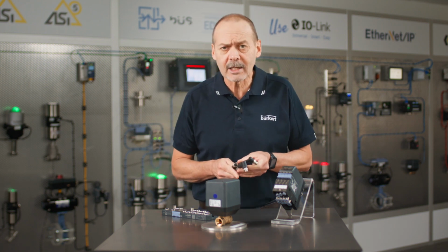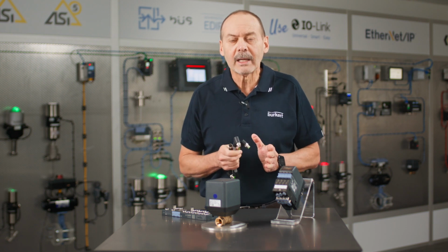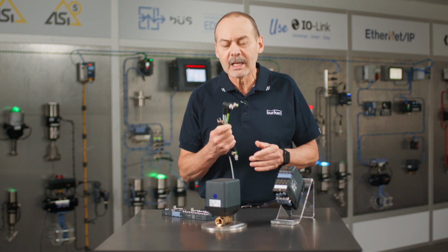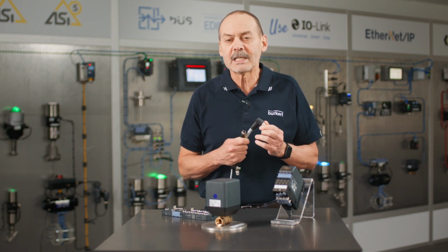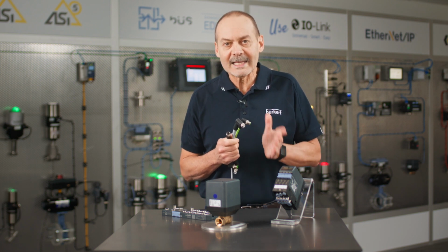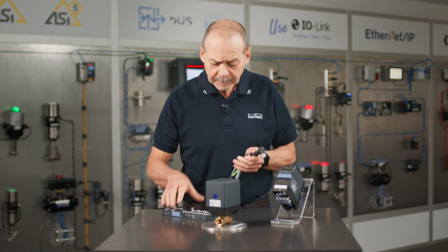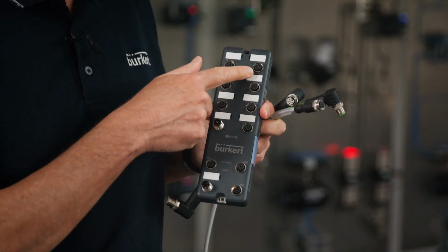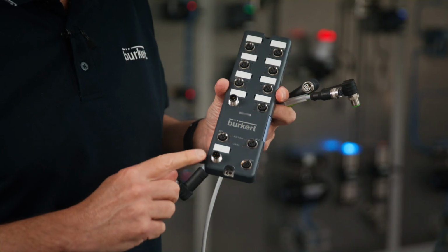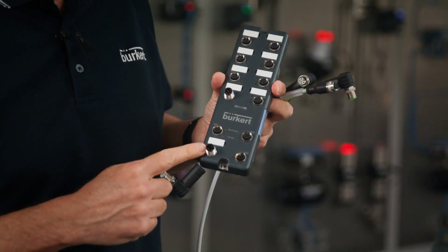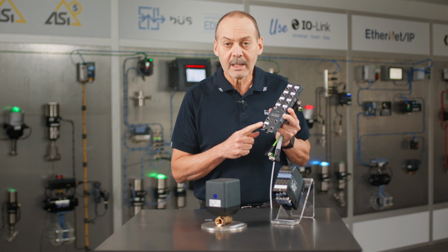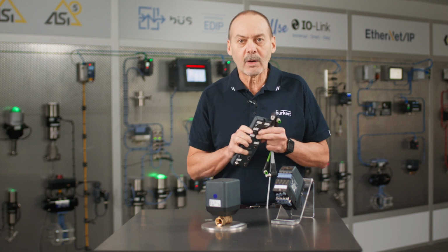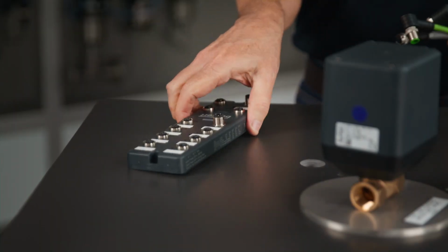The last one is an S-coded. That's another power distribution module. Looks fairly similar to the L-coded. However, it's a 3-pin and generally used only for AC power connection. As an example, you'll see on this block here, we have A-coded for our main connections, and we have D-coded for our Ethernet connections, and L-coded for our power. So you can't put any of the wrong ones in the wrong areas, so that's why we have the different codings for the different types.